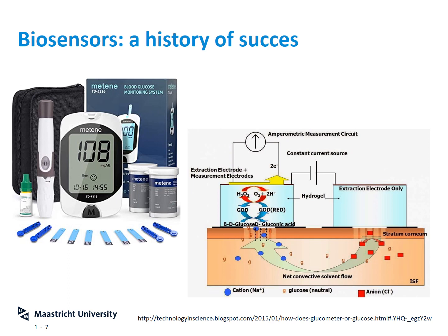And with that, hydrogen ions, 2H plus in the scheme on the right hand side, will be released. Now, when you insert this dipstick into a device, a glucose meter, which is actually just a very, very basic multimeter, what this multimeter does is apply an electrical field over the two electrodes. So when the hydrogen ions are released, they will travel inside the electrical field and make a current, because that is what current is, right? Ions moving in an electrical field. And the more glucose is present, the more current will be generated and the bigger the signal is. So your device will give a higher signal, and this can be calibrated to give the end user not a measure of how many amps are flowing, but actually the concentration of glucose that is there.